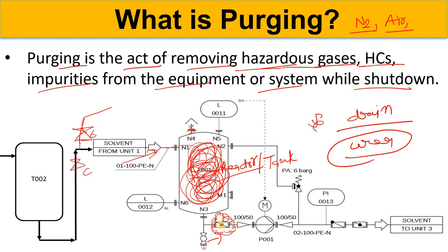The gate valve is simply closed, and we remove the condensate from the drain. When the ammonia or hazardous gases are eliminated, there are several methods to check — safety meters also come from the safety system to confirm the hazardous atmosphere has been eliminated. Once confirmed, you can hand over the entire equipment for maintenance. We also do purging before welding work to eliminate the combustible atmosphere.